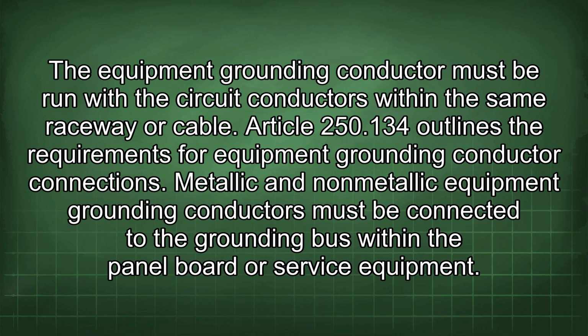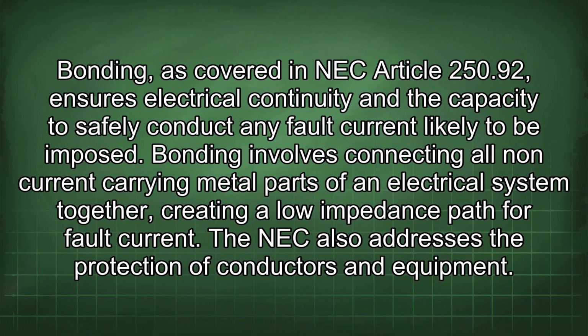Article 250.134 outlines the requirements for equipment grounding conductor connections. Metallic and non-metallic equipment grounding conductors must be connected to the grounding bus within the panel board or service equipment. Bonding, as covered in NEC Article 250.92, ensures electrical continuity and the capacity to safely conduct any fault current likely to be imposed.